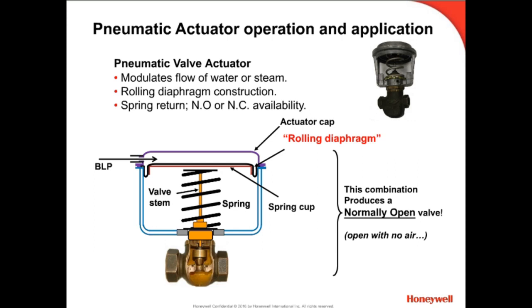The combination actuator and valve displayed here depicts a normally open configuration. That is, as branch-line air pressure is reduced, the spring pushes the stem up, lifting the stem and disc, and the valve moves towards open. If for any reason the air pressure is lost, the valve would go full open.